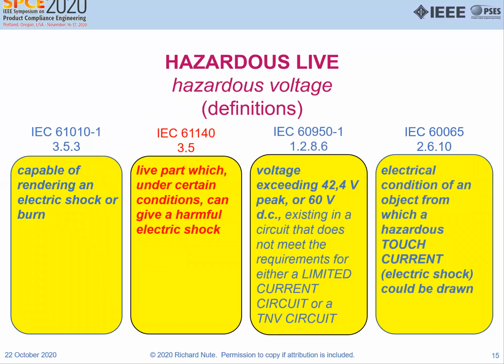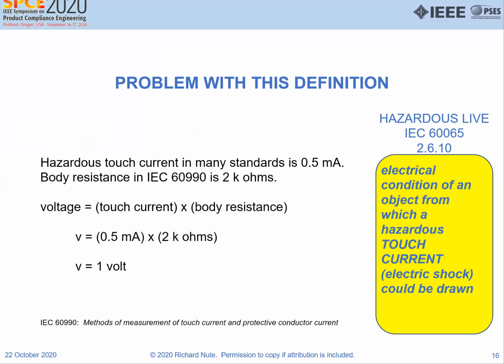Finally, we have 65, which says electrical condition of an object from which a hazardous touch current can be drawn. Well, that's a problem. We're going to see that that's a problematic definition, because if hazardous touch current in many standards is 0.5 milliamp, and the body resistance, according to 990, is 2,000 ohms, then applying Ohm's law, 0.5 milliamp times 2,000 ohms is 1 volt, which would mean that all batteries would be hazardous live under 65. Fortunately, 65 doesn't follow their own definition. That's okay.